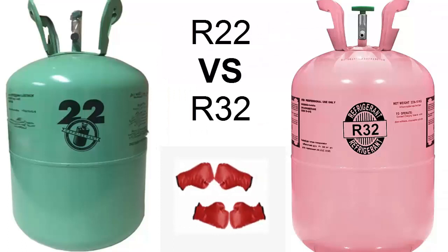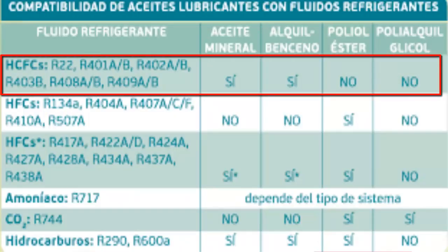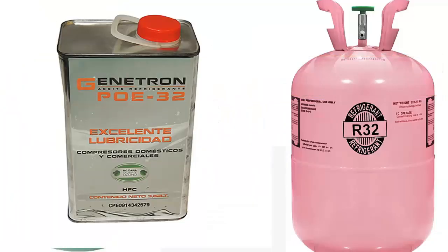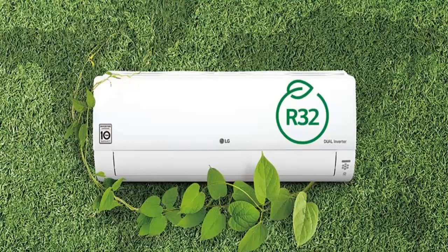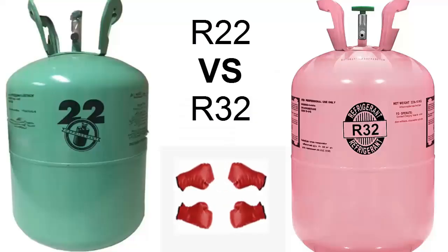Another significant difference between the two gases is their compatibility with different types of oil. R22 is compatible with mineral oil and alkyl benzene, but not with POE oil, whereas R32 is compatible and used with POE oil. R32 is a substitute refrigerant for air conditioning, only suitable for new equipment. This means that R22 should not be replaced by R32 in existing equipment.